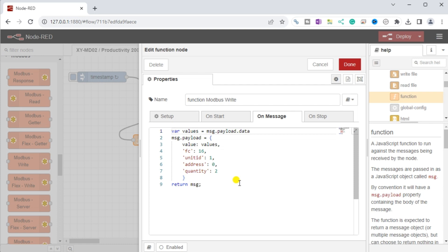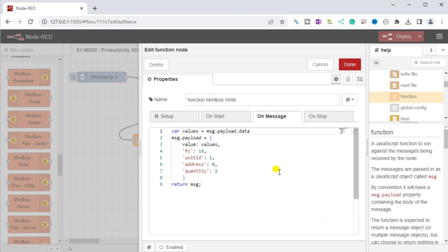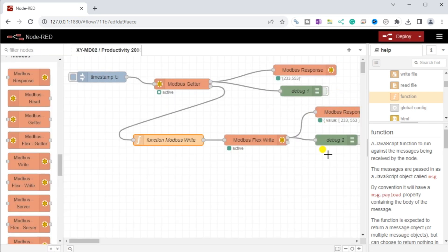The actual code that you see is JavaScript. We store the previous Modbus getter sensor values in a variable called 'values.' Creating the message payload for the Modbus flexwrite, it consists of the values for temperature and humidity, and also includes the Modbus function code, unit ID, address, and quantity. The function/Modbus flexwrite node is now configured to write the temperature and humidity values to the Productivity 2000 PLC. We can add Modbus response and debug nodes to our flow for troubleshooting.